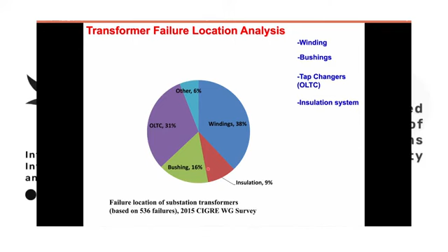According to a recent survey conducted by a CIGRE working group, about 38% of transformer failures are attributed to the winding of the transformer, low voltage winding and high voltage winding, followed by the mechanical part, which is the on-load tap changer, and then the insulation system and bushing. So it is very important to keep an eye on these components. If we find any fault during maintenance or condition monitoring, we have to rectify it as soon as possible to avoid catastrophic failure like the fire you have seen in the previous slide.